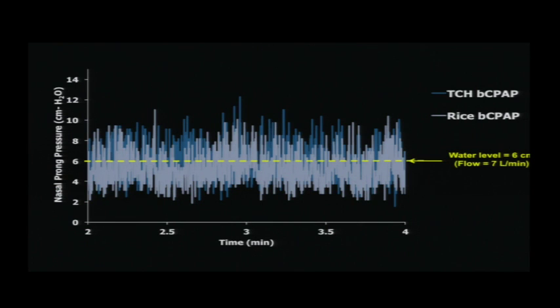So the first thing we tell our students to do is actually design your device, build it, and then test it and make sure it does what it should do. So what they did was they went to Texas Children's Hospital and they measured pressures and flow rates out of a bubble CPAP system used in Houston with babies that are premature. And they compared that to the pressures and flows that we got from our system. And what they found was really comparable results.